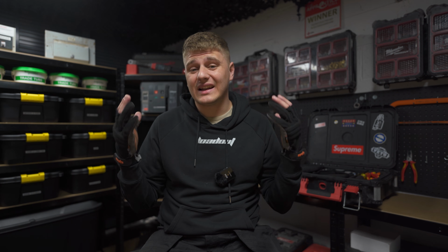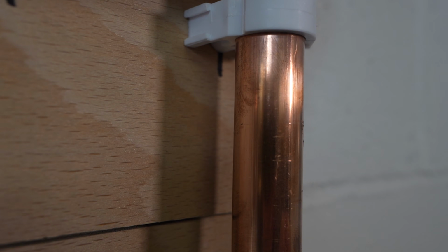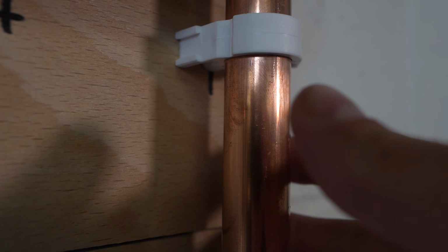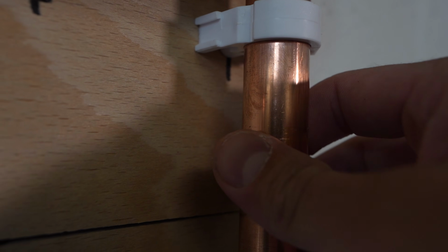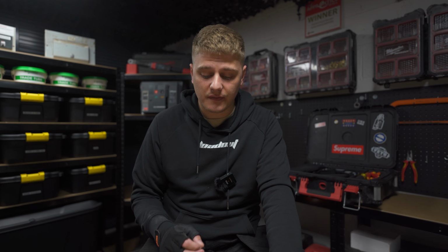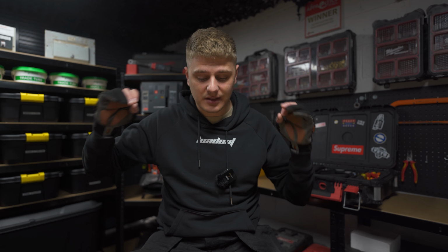For anyone that doesn't know what an extraneous conductive part is, the BS 7671 definition is a conductive part liable to introduce a potential, generally earth potential, and not forming part of the electrical installation. Now, you should pay close attention to the fact that it states not forming part of the electrical installation. So it's something that isn't associated or part of the electrical installation that's coming in, introducing a different potential than the potential of the electrical installation. So that's quite important.